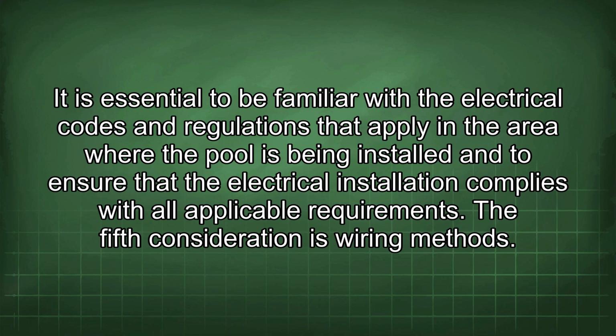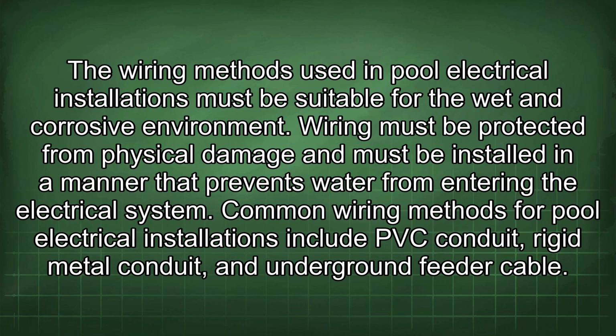The fifth consideration is wiring methods. The wiring methods used in pool electrical installations must be suitable for the wet and corrosive environment. Wiring must be protected from physical damage and must be installed in a manner that prevents water from entering the electrical system. Common wiring methods for pool electrical installations include PVC conduit, rigid metal conduit, and underground feeder cable.